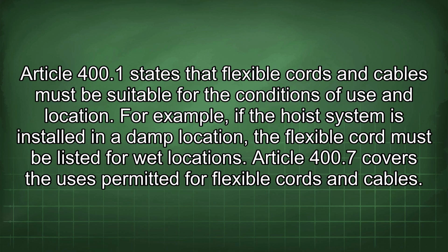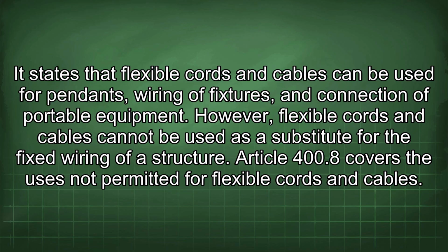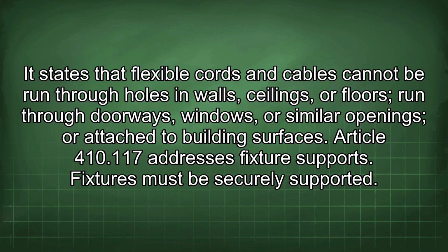Article 400.1 states that flexible cords and cables must be suitable for the conditions of use and location. For example, if the hoist system is installed in a damp location, the flexible cord must be listed for wet locations. Article 400.7 covers the uses permitted for flexible cords and cables. It states that flexible cords and cables can be used for pendants, wiring of fixtures, and connection of portable equipment. However, flexible cords and cables cannot be used as a substitute for the fixed wiring of a structure. Article 400.8 covers the uses not permitted for flexible cords and cables. It states that flexible cords and cables cannot be run through holes in walls, ceilings, or floors, run through doorways, windows, or similar openings, or attached to building surfaces.